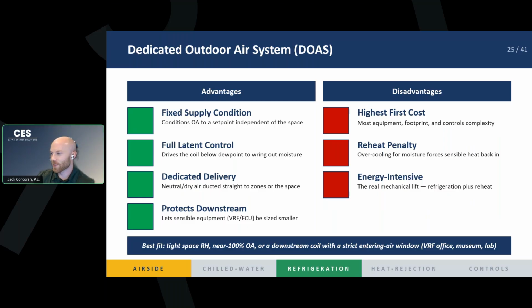But it does have some advantages. It has a much higher first cost, right? This is going to be an expensive piece of equipment, but if it's required and you need it, you need to have this piece of equipment that can deliver a precise temperature and humidity into your space or into the downstream coil. You do have your reheat. You are going to overcool because you're removing the humidity, and you need to have a reheat.